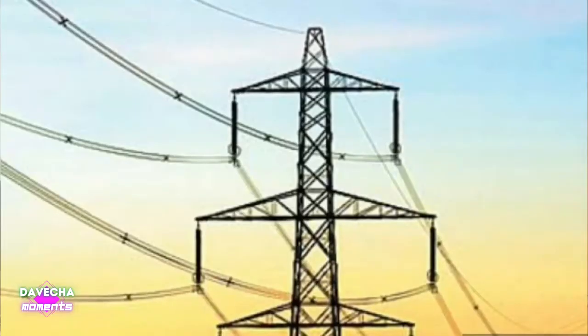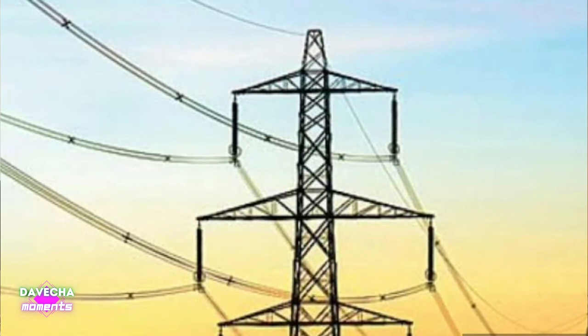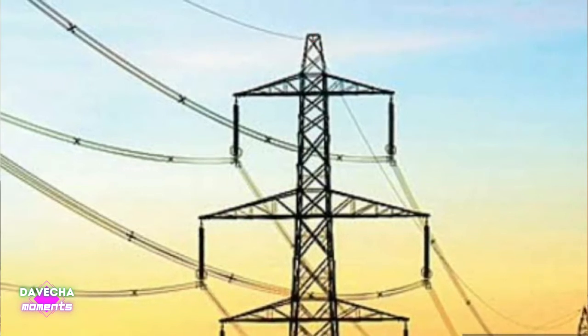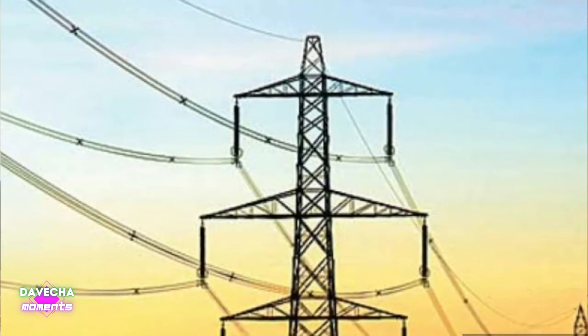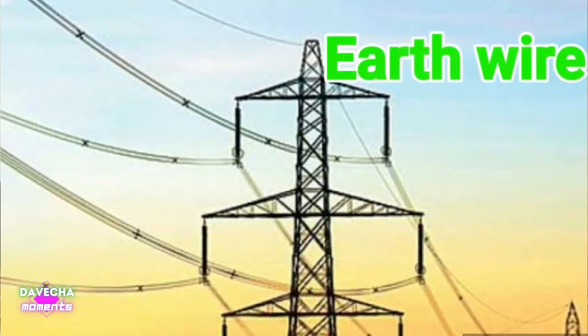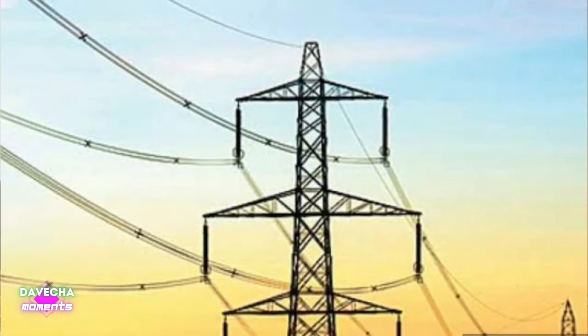In one of the previous episodes we did, we talked about power surge. One of the things that cause power surge is lightning strikes. In transmission lines, therefore, this has been factored in. We have conductors on top of the wires that have power in them, and these wires do not have electricity. They are called shield conductors or earth wires. If you have 4 wires, 3 have power in them. The fourth one, normally on top, protects the other conductors from lightning strikes. So those kinds of wires are called shield conductors.